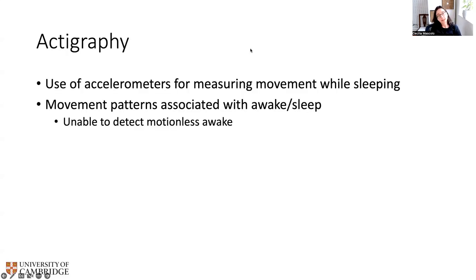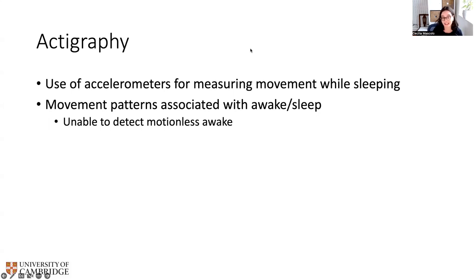One other technique that has been used is related to acceleration. Accelerometers measure movement — movement patterns associated with wake and sleep — so they detect wake and sleep quite well, but are often unable to detect motionless awake, and that's why this can be a problem. It tends to overestimate the amount of time you're sleeping.